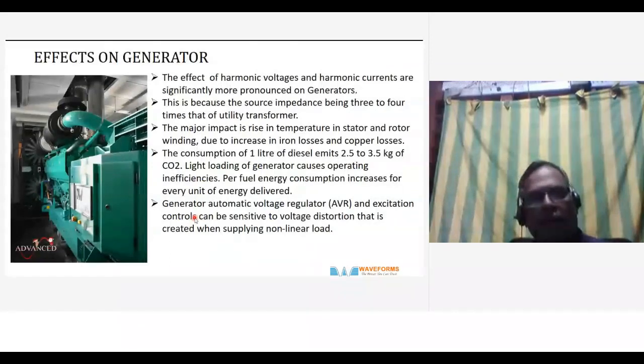So I think it is important to know the effects of harmonics on a generator. The effects of harmonic voltages and harmonic currents are significantly more pronounced on a generator. This is because the source impedance is 3 to 4 times that of a utility transformer. So that is important: source impedance being 3 to 4 times that of a utility transformer. So normally that is why you have to overrate the generator.